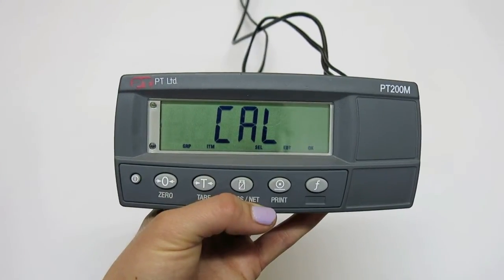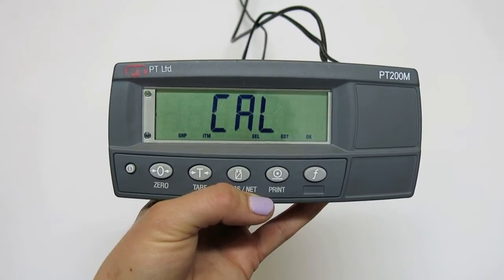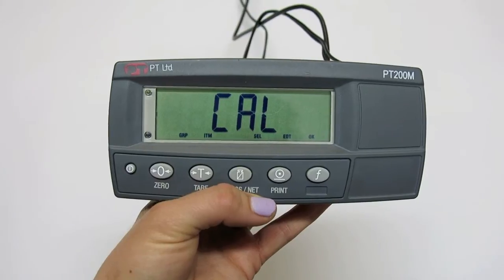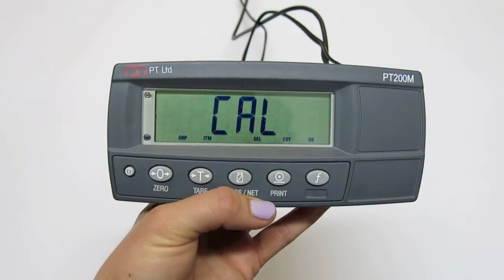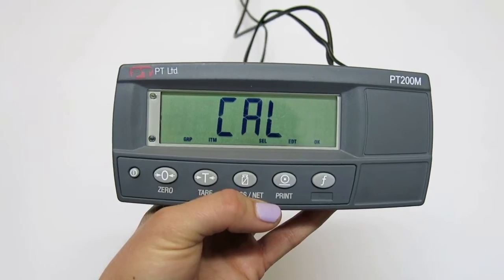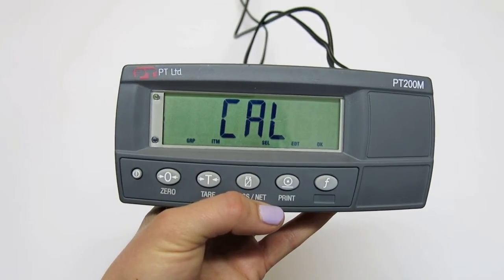Regular calibration can be used when you have a known weight to load onto the scale, using the corresponding change in signal for the calibration of the indicator. Both calibration methods involve two steps: zero and span calibration.